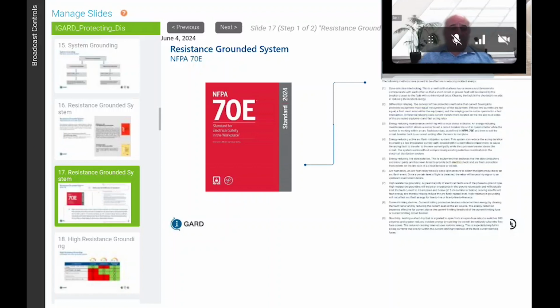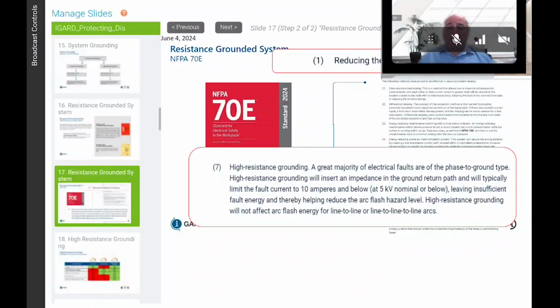So NFPA 70E and Z462 both say the same thing: reducing the likelihood of exposure. This goes to risk, where the risk of having an escalating overvoltage or arc flash on a solidly grounded system is extremely high. But put a resistor in place of that solid link, and now you have a high resistance grounded system. We've seen several documents showing that a high resistance grounded system will not escalate to a phase-to-phase fault. The book we saw at the beginning said that 95% of all faults begin as single phase to ground faults, and the majority of all electrical faults are phase to ground type. High resistance grounding will ensure that your fault will not escalate to a phase-to-phase or phase-to-phase-to-phase fault.